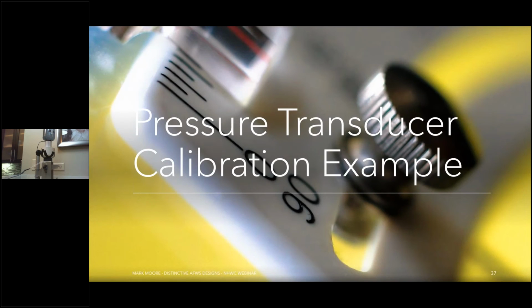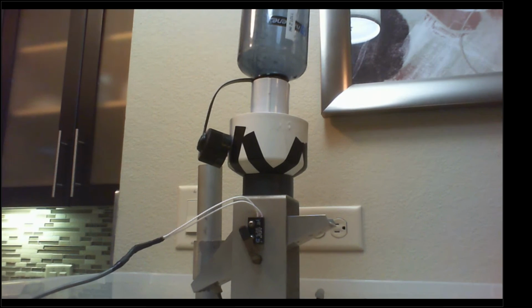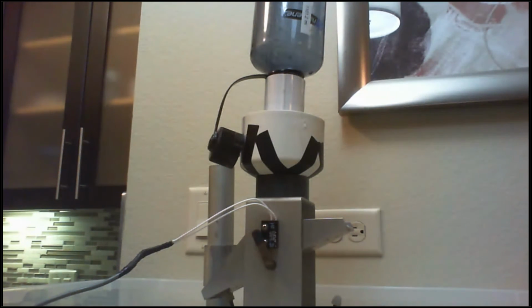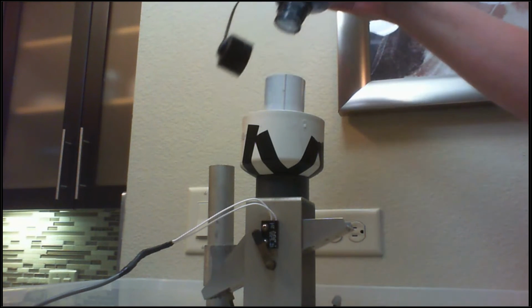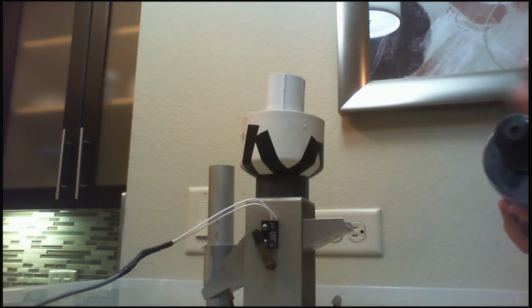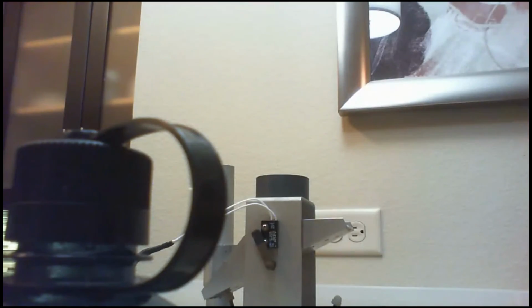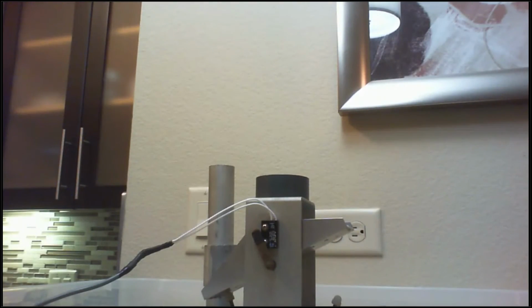That's a whole lot of words for calibration. So let's go ahead and actually do a PT calibration and just kind of see what we get out of it. So first off, I'm going to stop sharing my screen. Go back to our tipping bucket, which I'll take a quick moment to show that we got to 14 tips. It should have been 15 tips. So we get that out of the way. We're slightly underreported. We should have been at 15 tips, but we only got 14 tips.